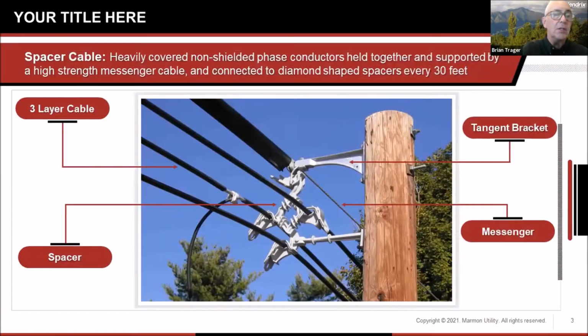Very quickly, what is spacer cable? It's heavily covered, non-shielded phase conductors held together and supported by a high-strength messenger cable and connected to spacers every 30 feet. You can see the messenger up on the top there. That's a mechanical support member. It holds everything up in the air. It's also a system neutral. It's also a lightning shield, and it holds everything off the phase conductors that may fall on them from on top, whether that's trees or what have you. You see we've got a spacer every 30 feet, every 10 meters. A couple of brackets, a tangent bracket, angle bracket, dead end bracket, and that's it. It's a very simple system.